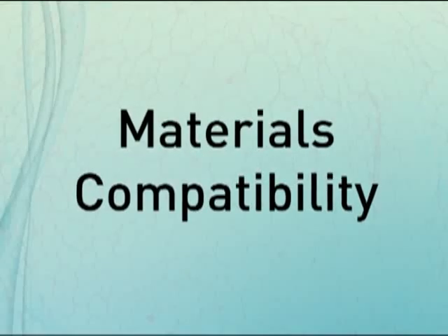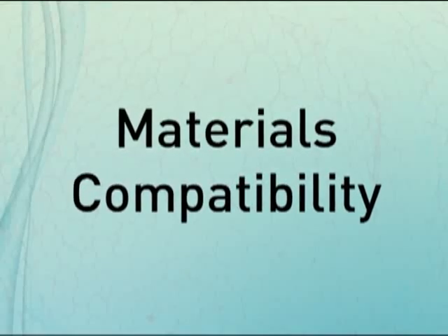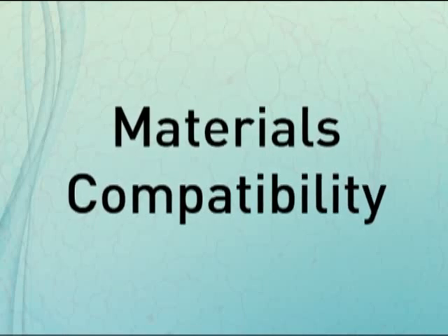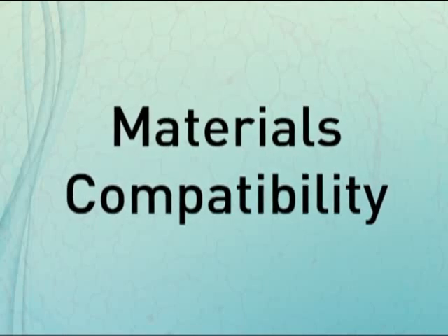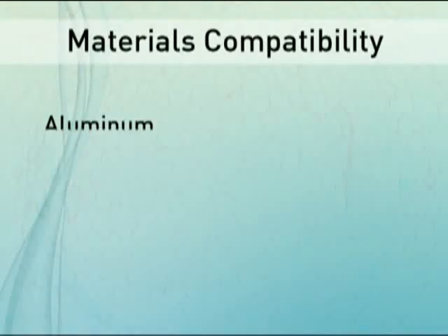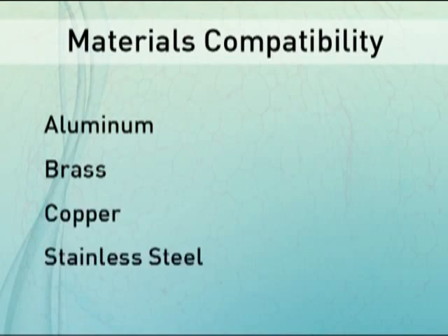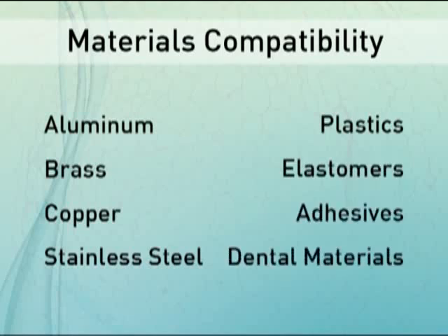Cidex OPA solution has excellent compatibility with a very wide range of materials commonly found in medical devices, including aluminum, brass, copper, stainless steel, plastics, elastomers, adhesives, and dental materials.